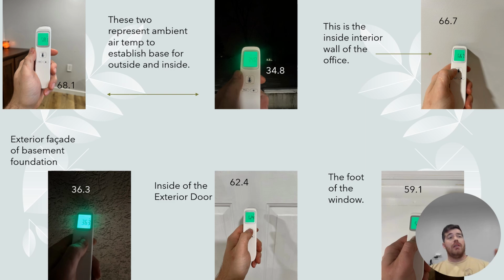If you look into the top left of the slide, we have our two bases. We have a 68.1 inside ambient temperature and a 34.8 outside ambient temperature. So, pretty spot on with the inside ambient, based upon the zone and the heating that the thermostat is set at. Next, on the far right, this is the inside interior of the office, the wall that's facing the inside towards the house. It is 66.7. So we have a little bit of loss there, but nothing bad. It is holding tight. The insulation is doing its job.